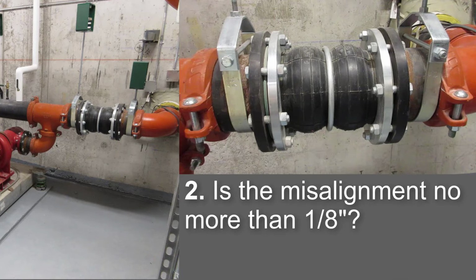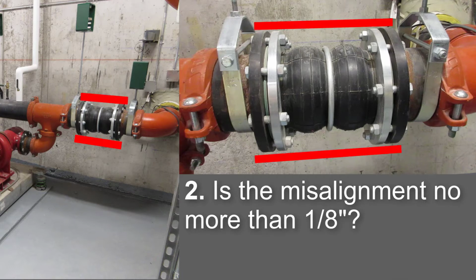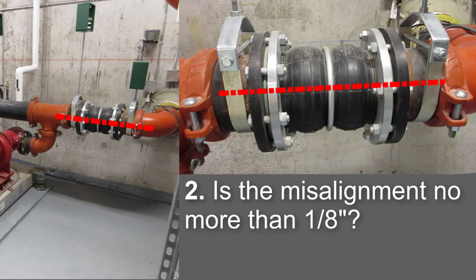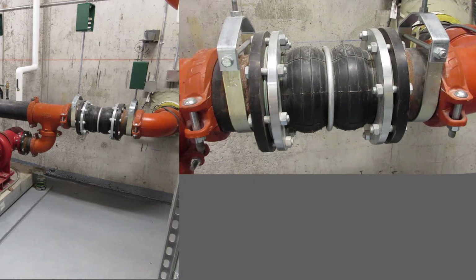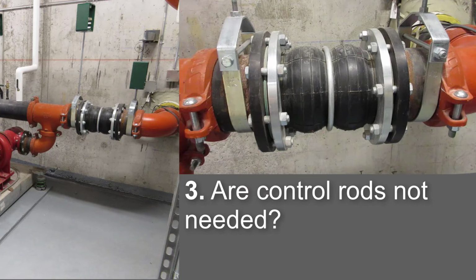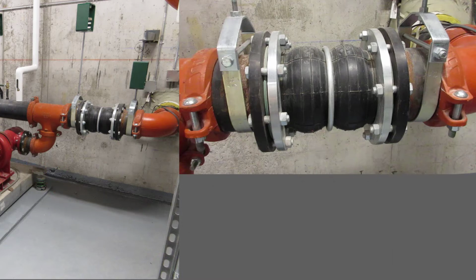Second, is the misalignment less than 1/8 of an inch? Based on lining up the flanges on either side and considering the center lines of the pipes on either side, it certainly appears to be collinear. No discernible offset, so this is okay. Third, are control rods not needed? The pipe appears to be solidly connected to the pumps on one side and it goes through a wall on the other side, so there appears to be very little opportunity for the pipe to move much. There doesn't appear to be any reason to add control rods here, so it's okay as is.